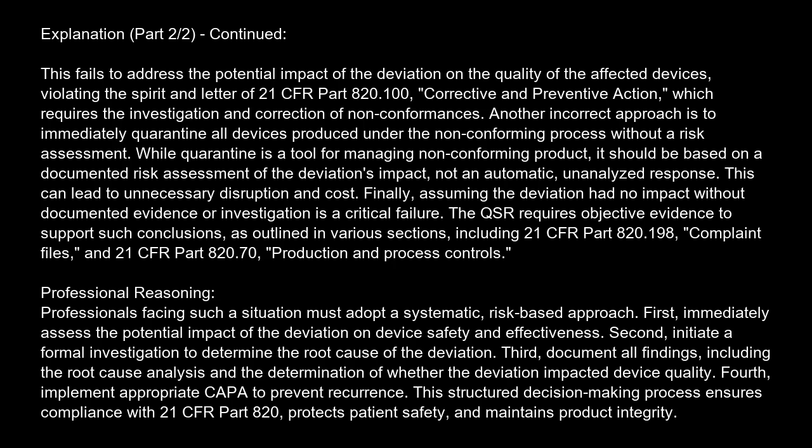Finally, assuming the deviation had no impact without documented evidence or investigation is a critical failure. The QSR requires objective evidence to support such conclusions, as outlined in various sections, including 21 CFR Part 820.198, Complaint Files, and 21 CFR Part 820.70, Production and Process Controls.